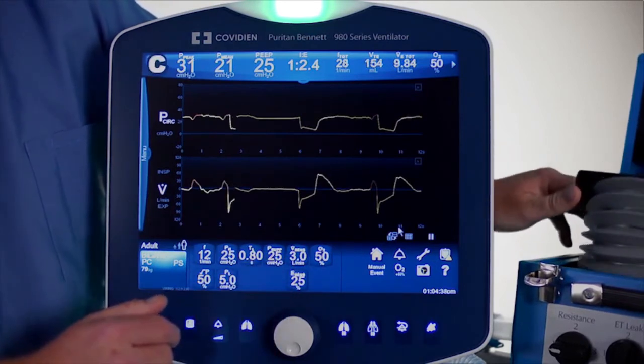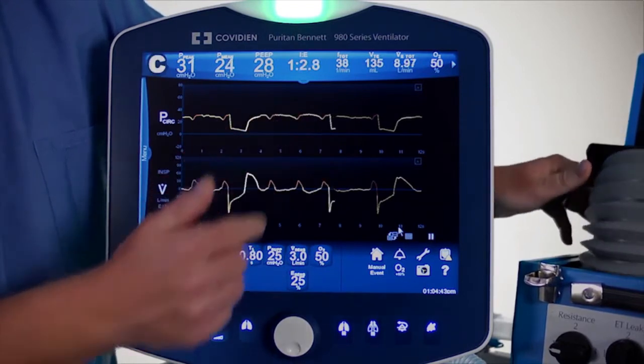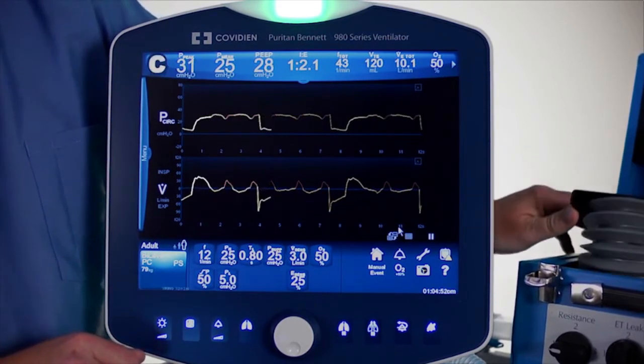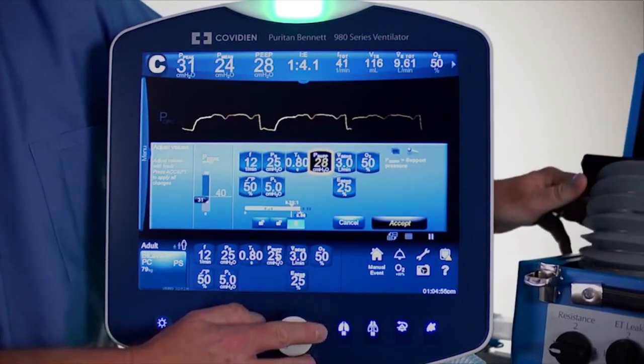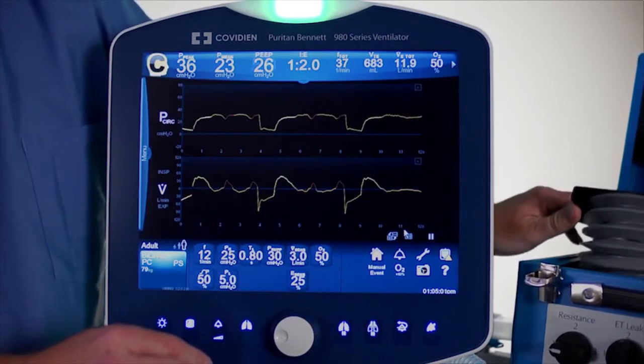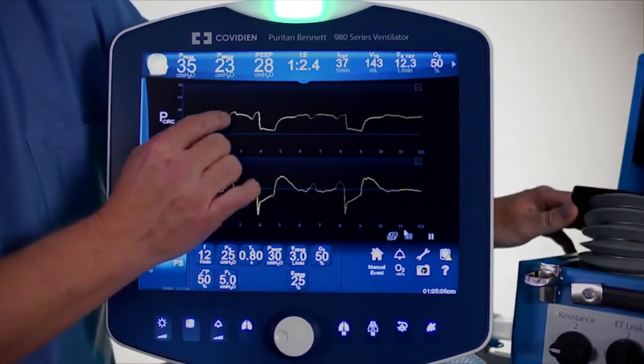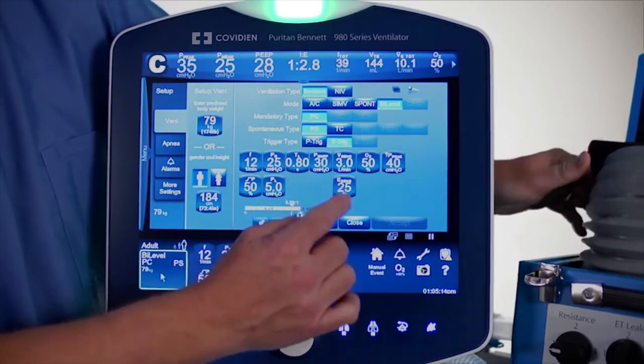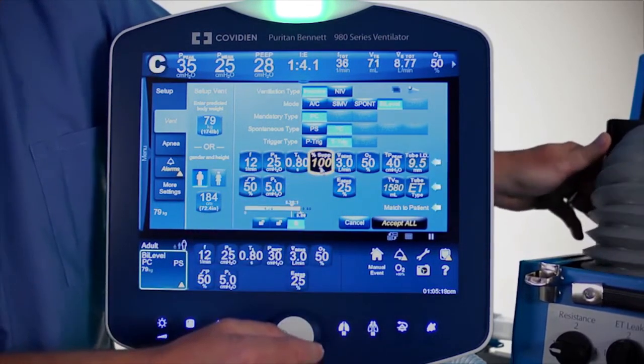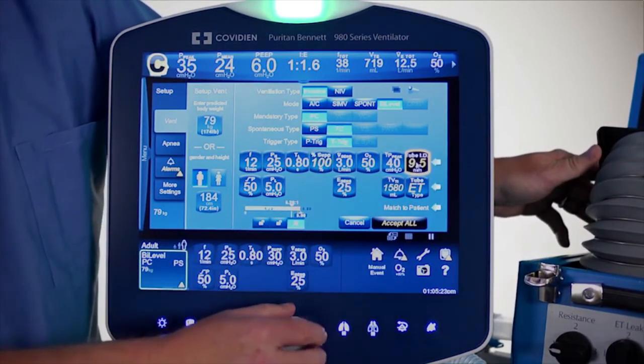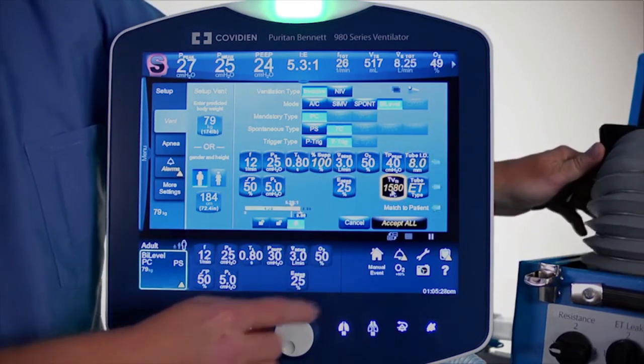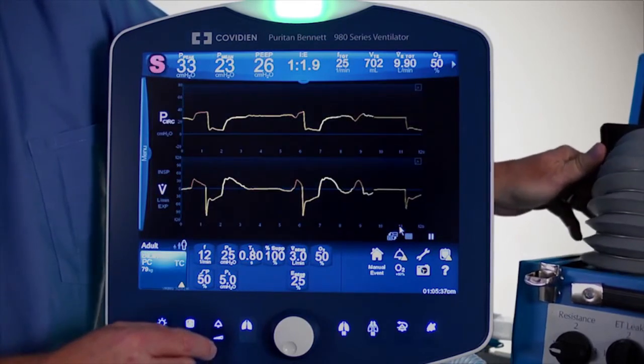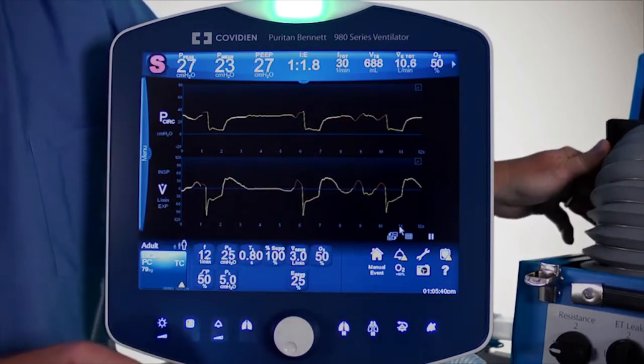Increasing pressure support up to 25, when the patient takes a spontaneous breath he now gets a little bit of pressure support at the top — our peak pressure on spontaneous breaths goes up to 31. You can augment spontaneous breaths by increasing pressure support, keeping in mind limits on peak pressure for each patient. You can also turn on tube compensation instead, setting the percentage of support, the inner diameter of the endotracheal tube, and selecting whether it is an ET tube or trach tube. This provides whatever pressure is needed to overcome the imposed work of breathing from the artificial airway.